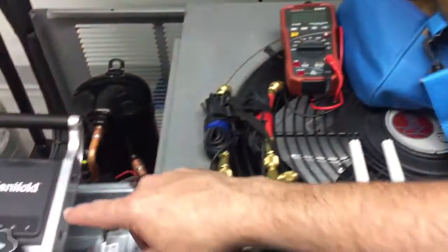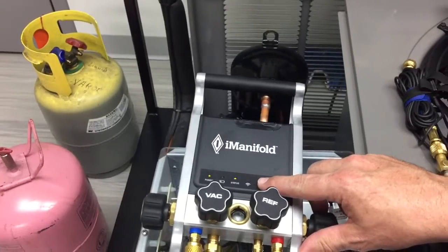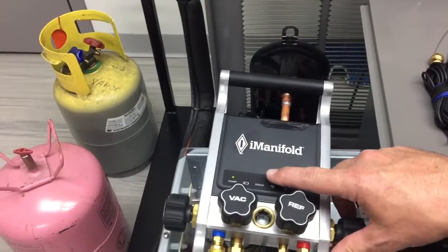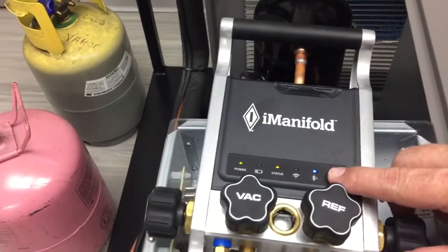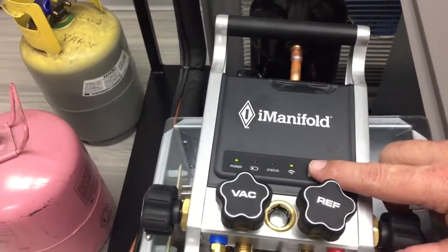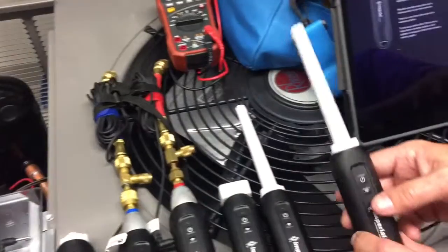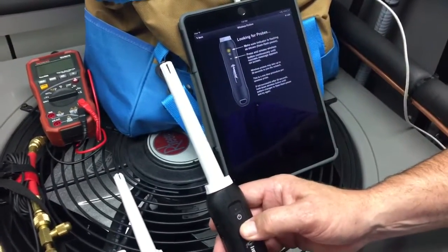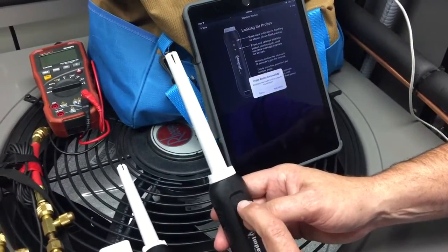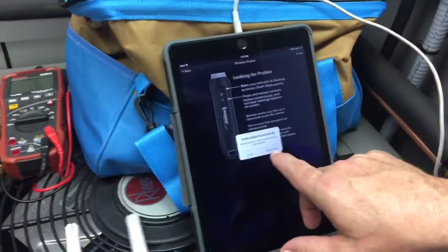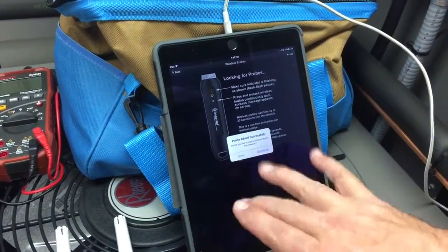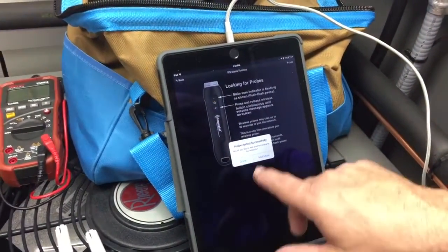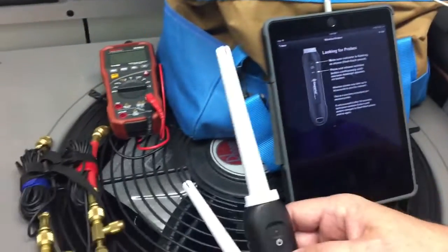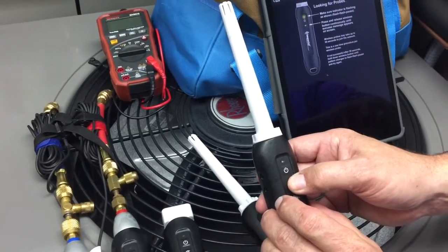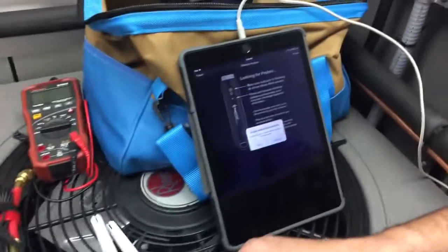Over here on the iManifold, you'll see that the wireless icon is now fast flashing. We've got the status light, we're connected via Bluetooth, and the wireless is looking for wireless probes. Now all I'm going to do is take one of these probes and tap the wireless button one or two times. You can see it's now fast flashing, and that probe is added successfully. I don't really have to touch anything here to add more. I can tap this and it'll clear that out, and then tap this again to get the next probe in the network.